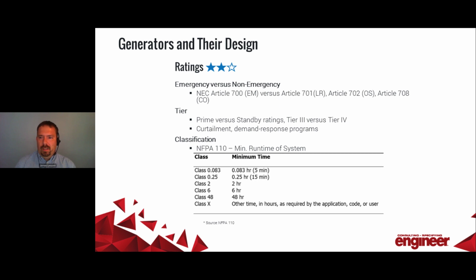Sometimes you'll find in some markets, the utility company will offer a curtailment or a demand response program where they have different rate structures for peak versus non-peak power. And there's opportunities to save some money by shaving some demand off during peak hours or whatnot. In that arrangement where you're frequently using the generators to generate power, you're in a prime situation, and you need to be Tier 4 EPA classification, or I should say tier, because below that, NFPA 110 sets up classifications.